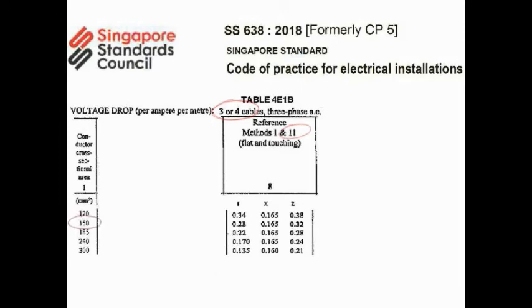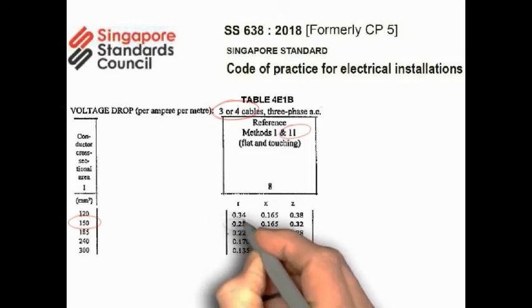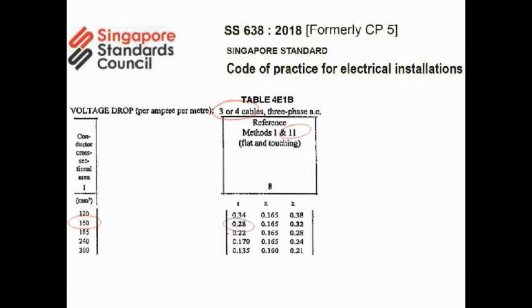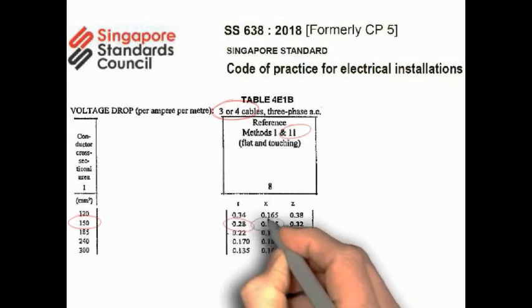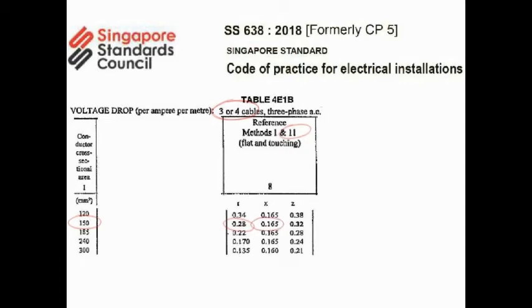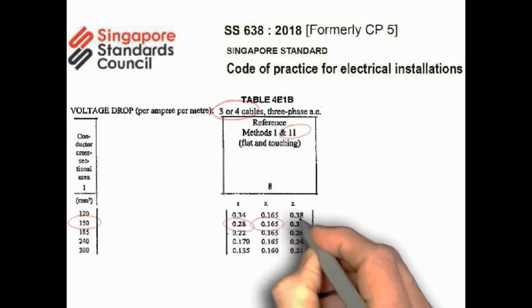For a cross-sectional area of 150 mm squared, we have three values in place: R, X, and Z. R refers to the resistive voltage drop, X refers to inductive voltage drop, and Z is the impedance voltage drop. This value can be used in the calculation model later. From here, we see that R is 0.28, X is 0.165, and Z is 0.32.